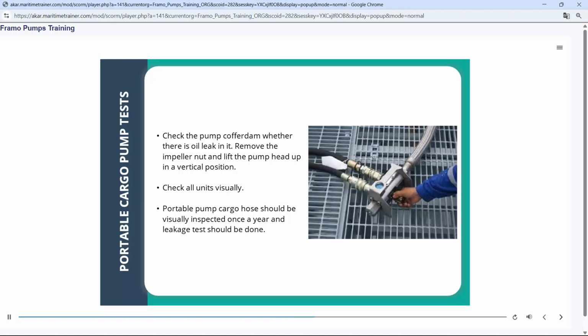Check all units visually. Portable pump cargo hose should be visually inspected once a year and a leakage test should be done.